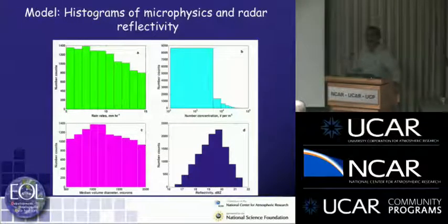This is an end-to-end calibration that could be done. You can't claim to calibrate the radar just using drizzle measurement, but this could be verified independently. I'll show you how we can do this. In general, if we calibrate a W-band system, then we can look at the light drizzle and do this calibration. This is very interesting. There is published work on this in JTECH, on how they have done it. The only problem is that any time the radome gets wet, there is a lot of absorption because of the wetness of the radome. You need to be careful and protect the radome. Also, this could be done only in ground-based mode, not on an airborne platform, which is much more difficult, unless the radome is not wet.